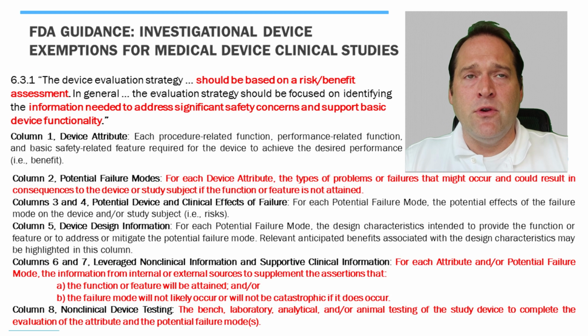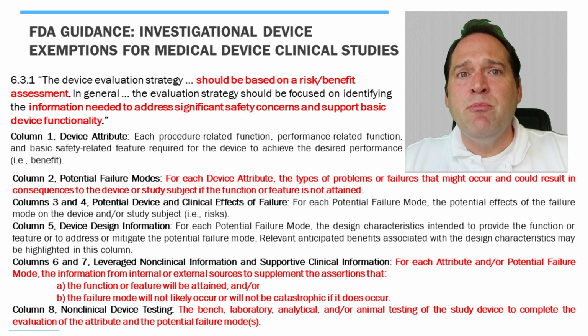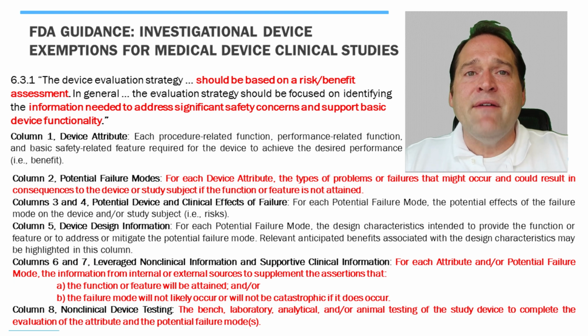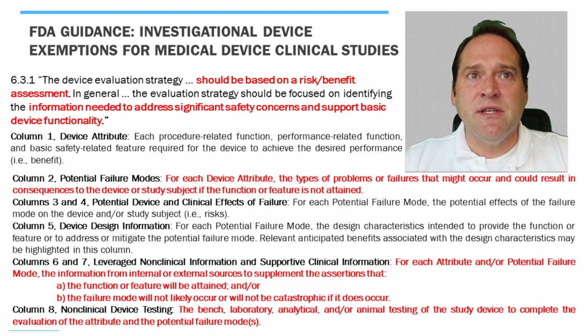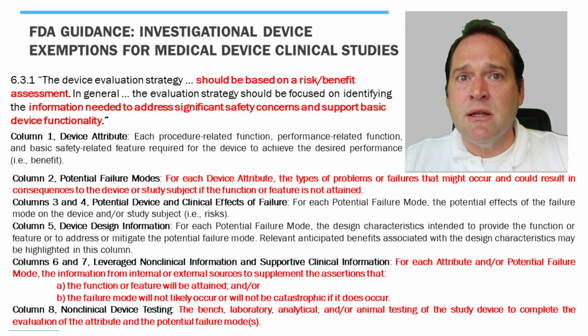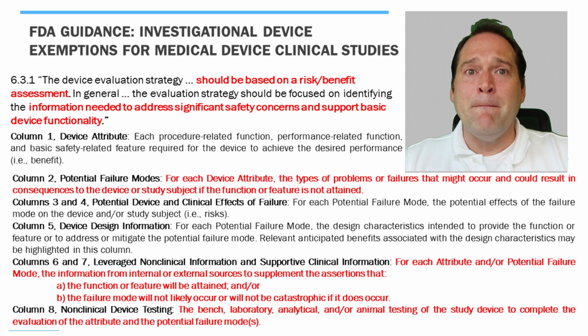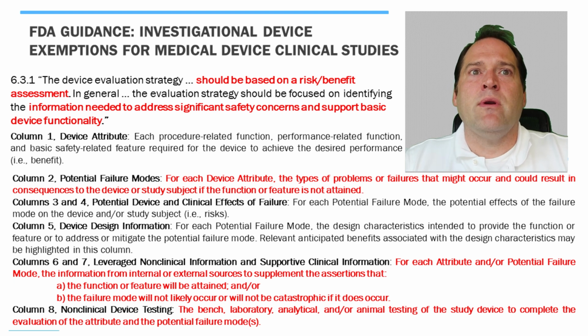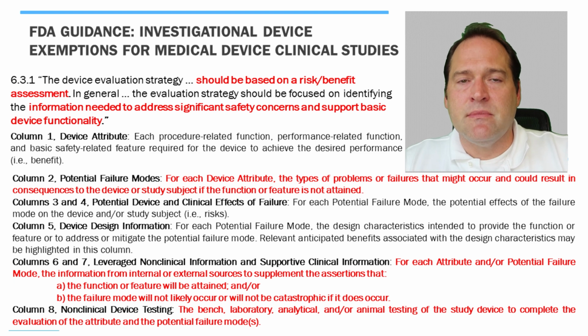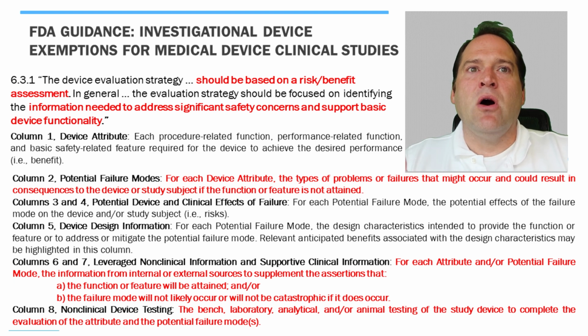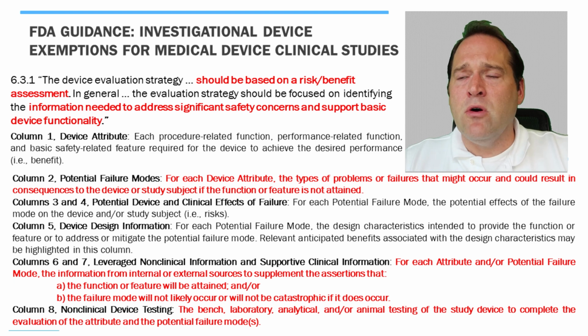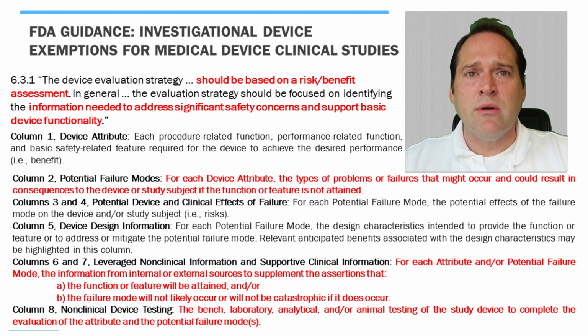So the language you see in front of you is drawn directly from the FDA guidance on investigational device exemptions. There are a couple of key points I want to go over, but I don't want to read this to you word for word. I've highlighted most of the key points in red. As I said previously, the device evaluation strategy should be based on a risk-benefit assessment. It should include information needed to address significant safety concerns and support basic device functionality. So the way you do this is often in a table format, and you start out in one column with just the device attributes. Then in column 2, you talk about the potential failure modes. This is actually often overlooked by people who haven't done this much, and it's really the most important point in terms of how to prepare for an IDE.